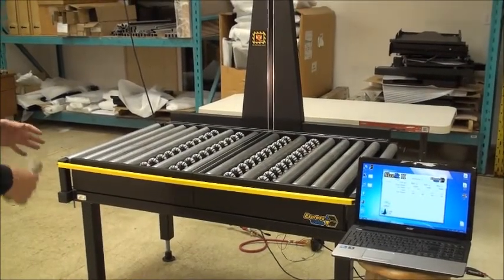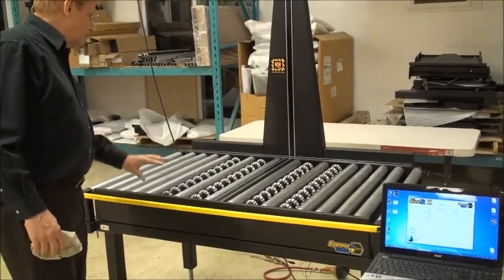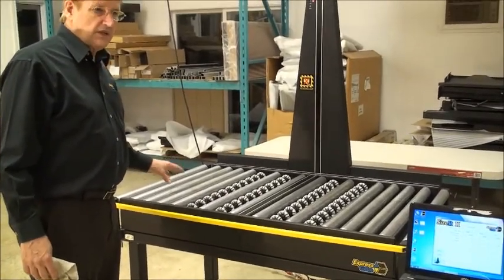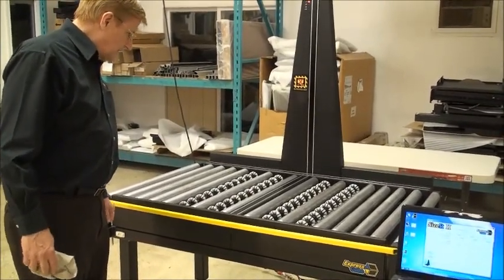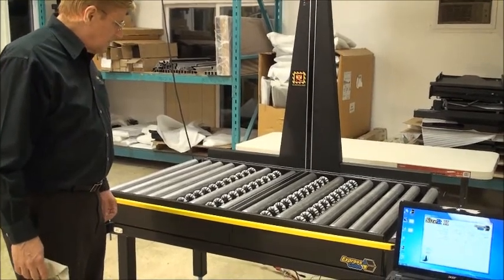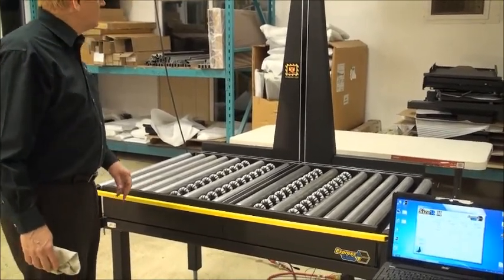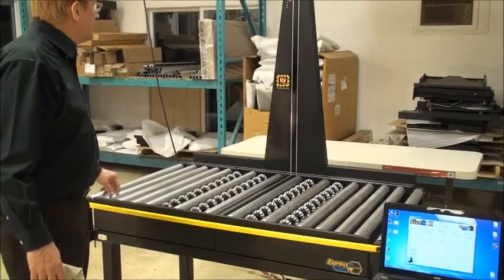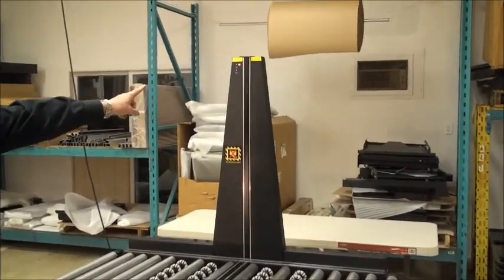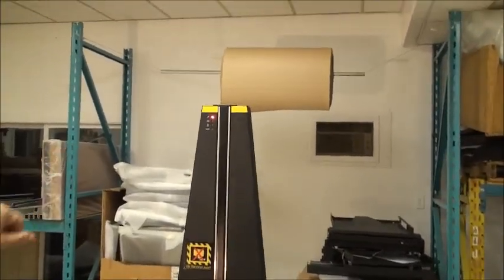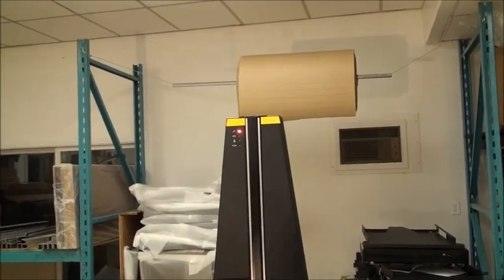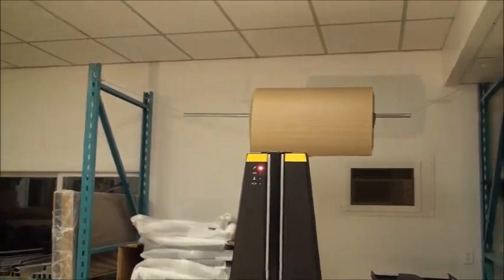All right, what I'm going to do is show you when you're starting to do your measurements with the machine. It could be first thing in the morning or whatever, the machine setup. Now right now what you'll notice is that there's nothing on the table. The machine is indicating red. If you check the computer SizeIt, it will show you that there's actually a negative weight on there.